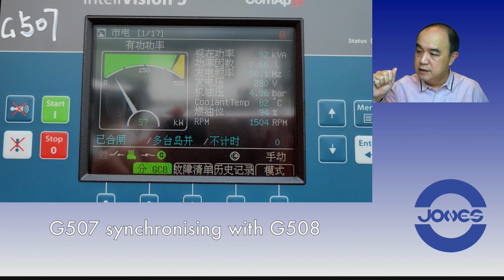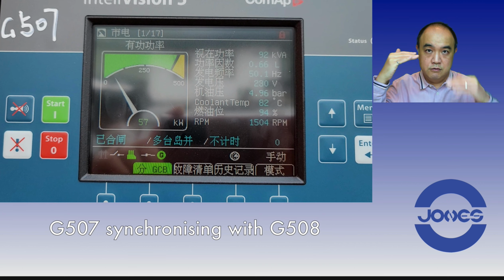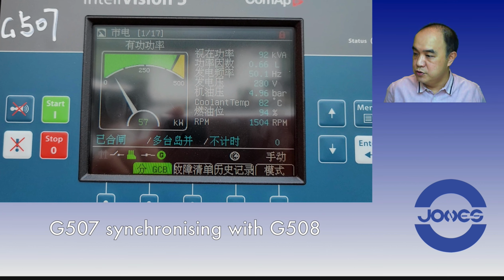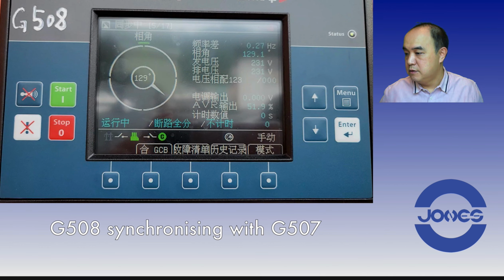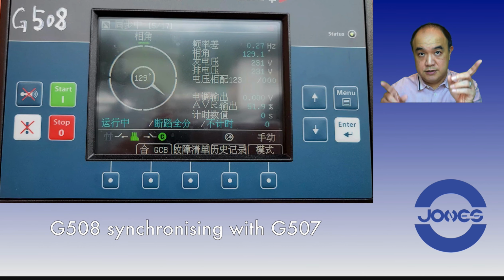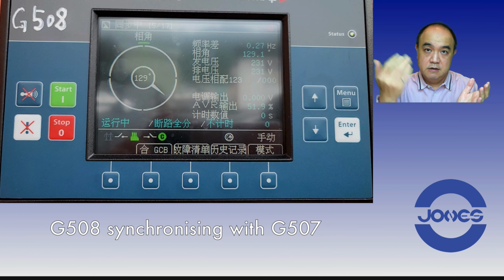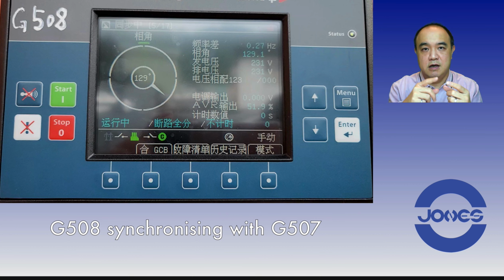You can hear that, and then immediately afterwards the gensets start to load share, and I showed you that the load sharing is quite even between the two sets. So to make the test complete, of course I need to test the other way around, so I took G508 off the bus. So only G507 is running now with the same settings, 9 degrees, 0.2 seconds. I tried to close 507 to 508.